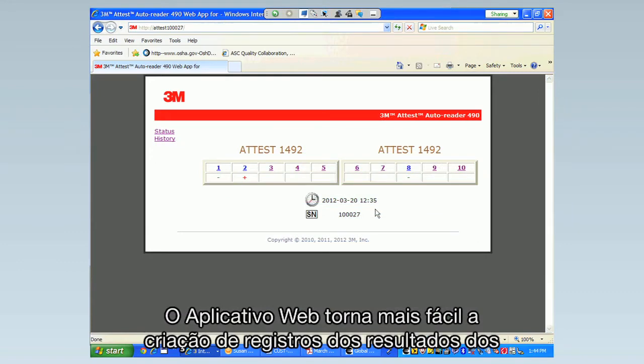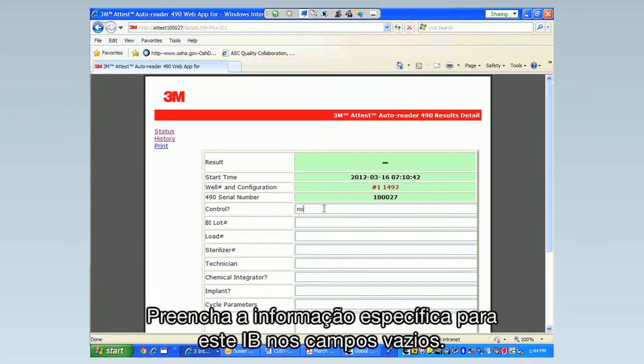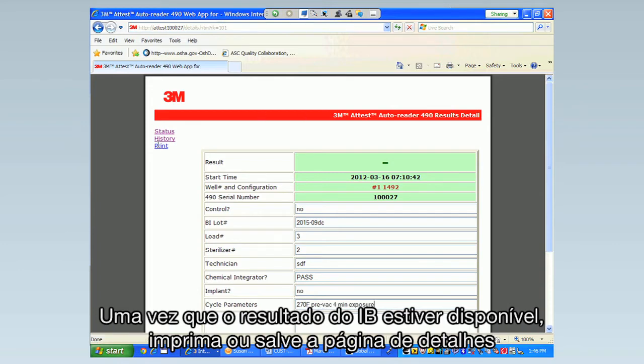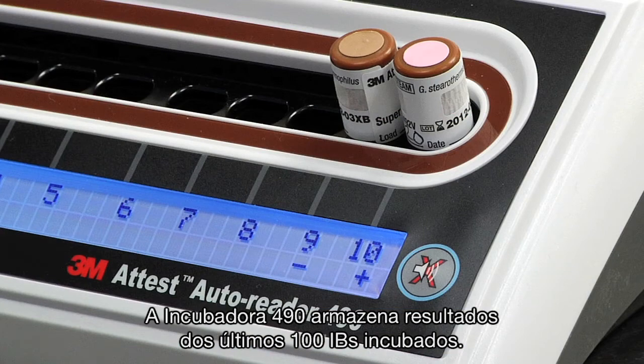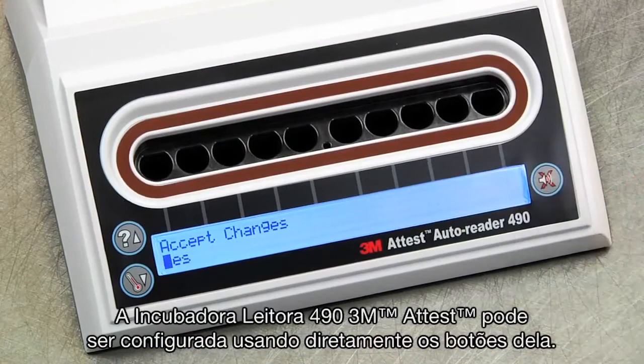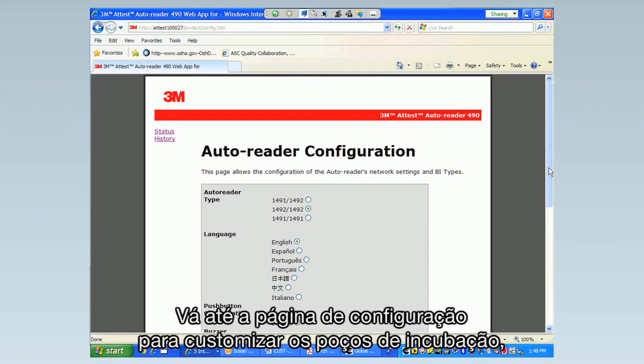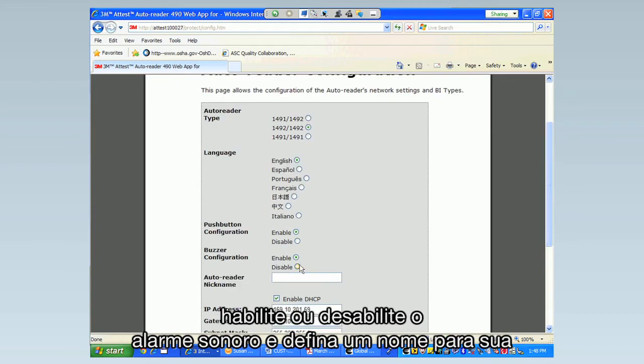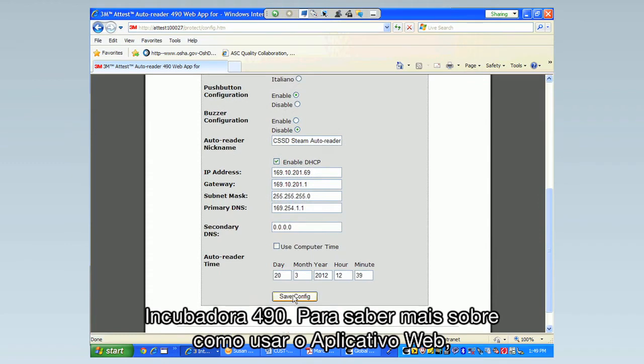The Attest web app makes it easy to create records of BI test results. After inserting a BI in the Attest Autoreader 490, open the results detail page for that BI by clicking on the corresponding well number from the status page. Enter the specific information for that BI in the empty form fields. Once the BI result is available, print or file the results detail page to create an individual record for the incubated BI. The Autoreader 490 stores results for the last 100 incubated BIs on embedded software, and the web app history page provides a summary of these results. You can also configure the unit remotely using the Attest web app — go to the configuration page to customize incubation wells, enable or disable the audible alarm, and assign a nickname to your Autoreader 490. See your operating manual to learn more.